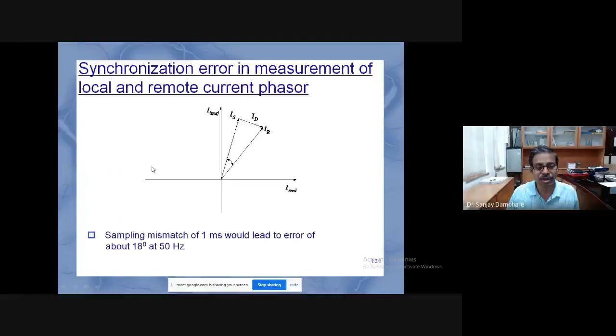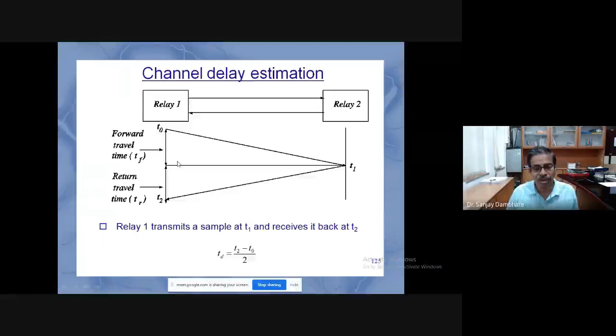So I have already said that this was the first attempt to use differential protection for transmission system protection. This slide is showing that if the sampling is mismatched by 1 millisecond, then you will get 18 degrees at 50 hertz, and that will be sufficient to trigger the relay. The transmission of the signal and the time delay, that is the latency, will also play an important role. But if the signals are time synchronized, then we will not go for the computation of the forward travel time or the return travel time, but we can certainly try to align the signals with the same time tag. That is what I'm saying.